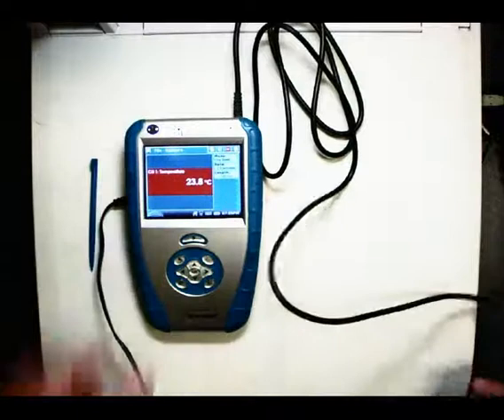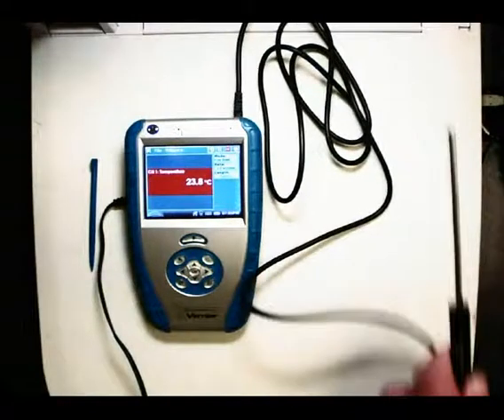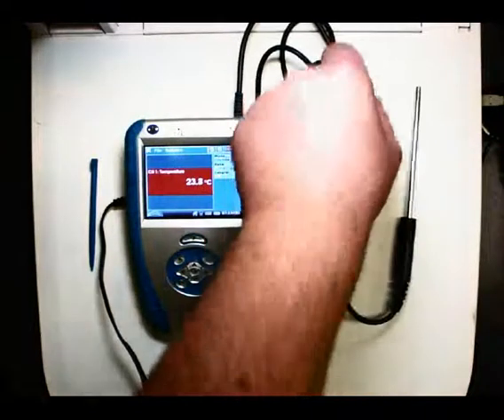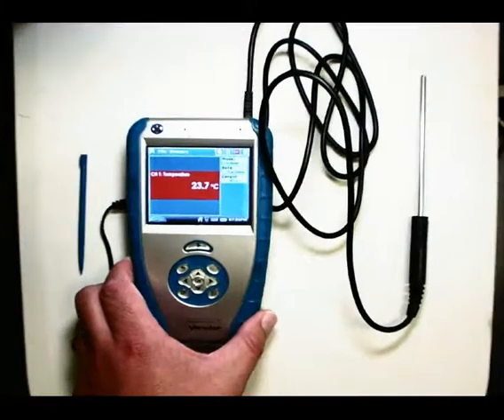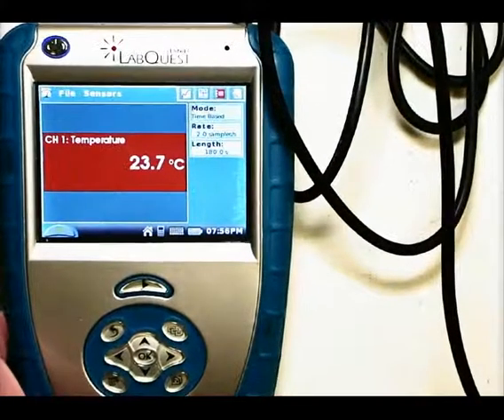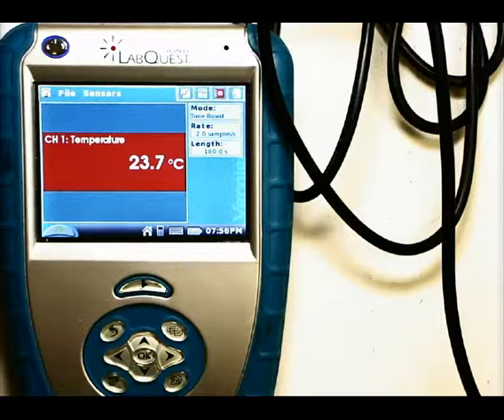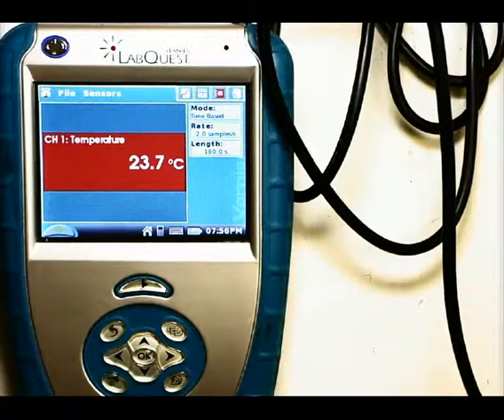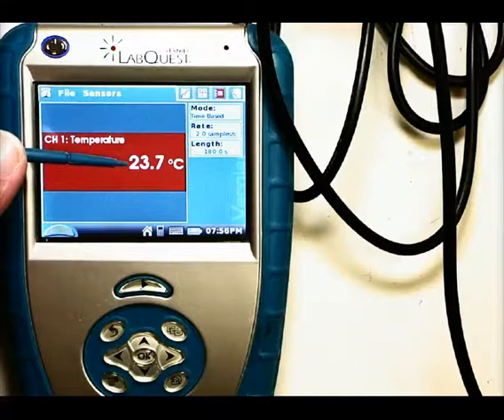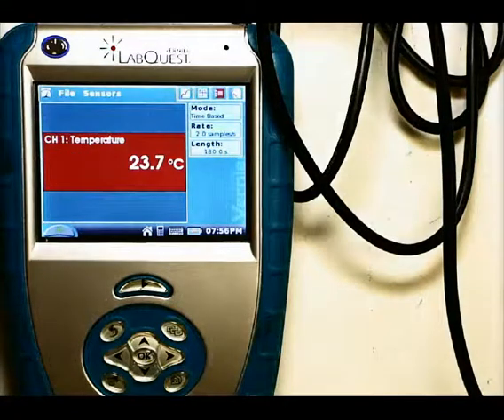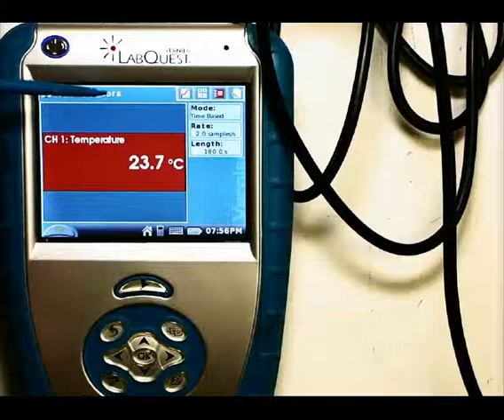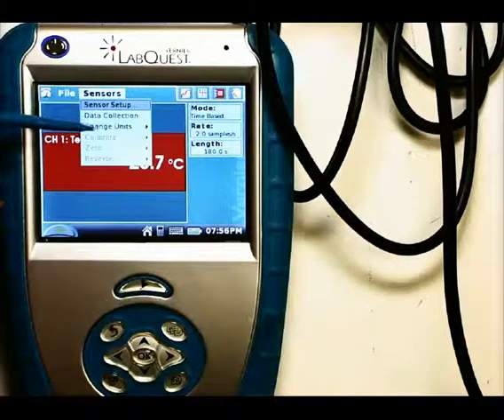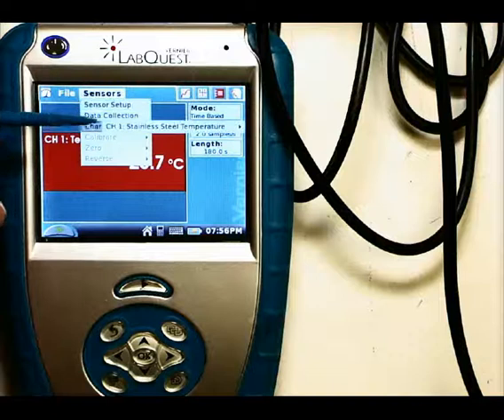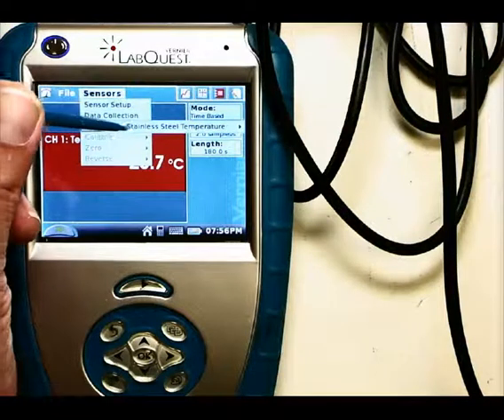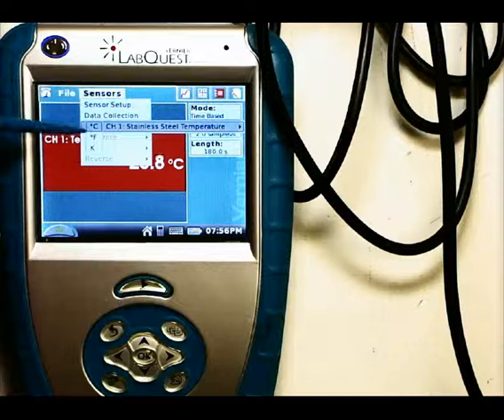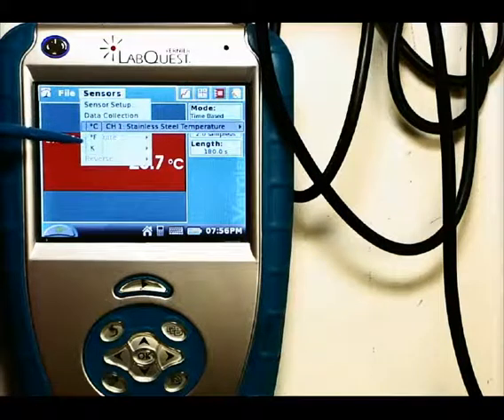And you can see immediately that the LabQuest has started doing some work. I'm going to zoom in now so we can see what's going on here a little bit better. So here we have the probe measuring temperature, and right now it's a temperature of 23.7 degrees Celsius. If we want to change that, you can click on the sensor menu, and then you'll see a spot that says change units, and then you'll select what instrument you want to change. So for the temperature, I can collect in Celsius, Fahrenheit, or Kelvin.